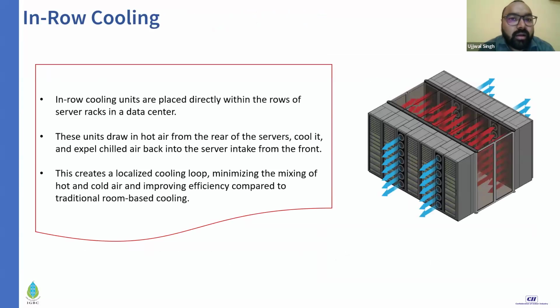Now, just like in cold air containment technology where the cooling system is in a mechanical gallery placed at some distance from the server, here we bring that cooling system adjacent to your server rack. So there are, say, two server racks, then one cooling unit, then two more server racks, and one cooling unit. This helps because the hot air generated from your containment zone will be sucked in by your cooling system right then and there.